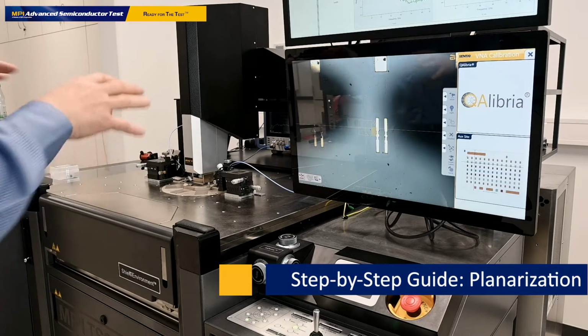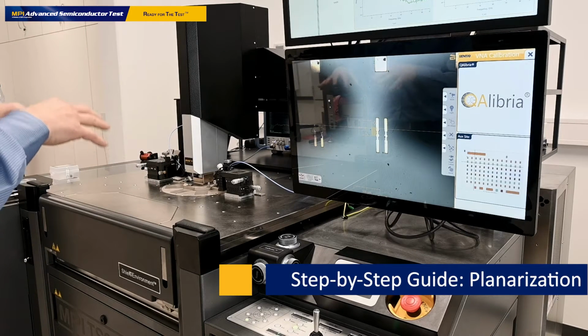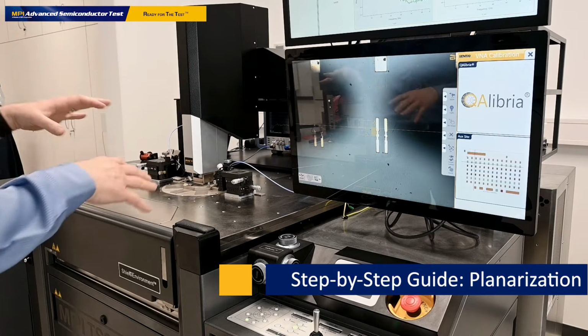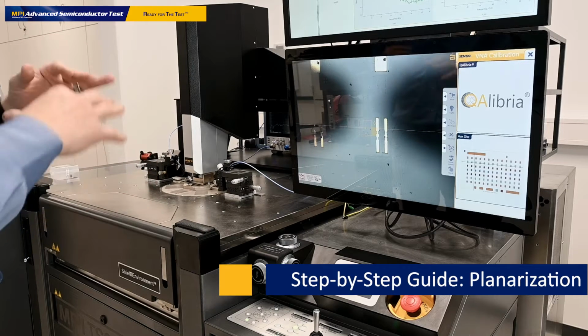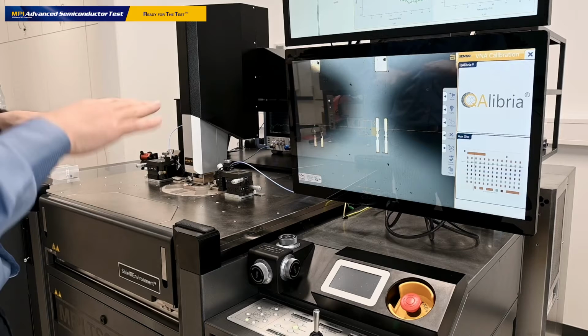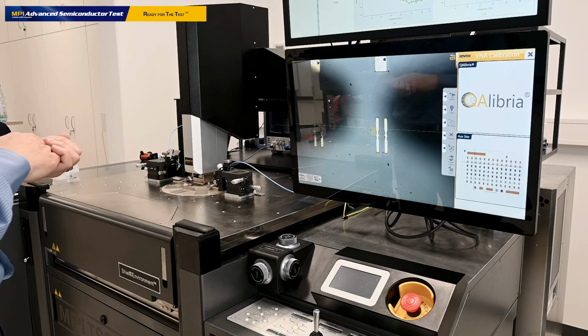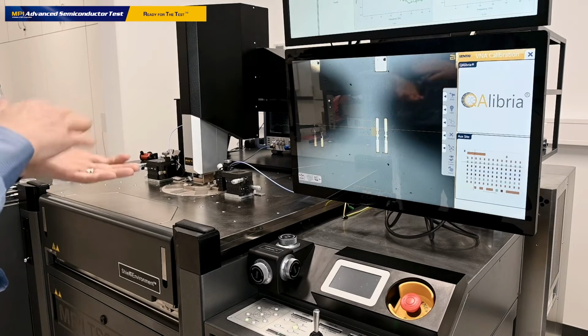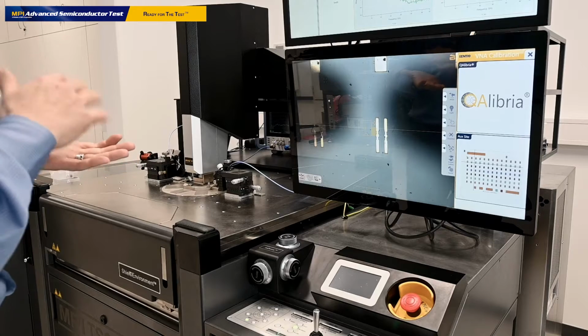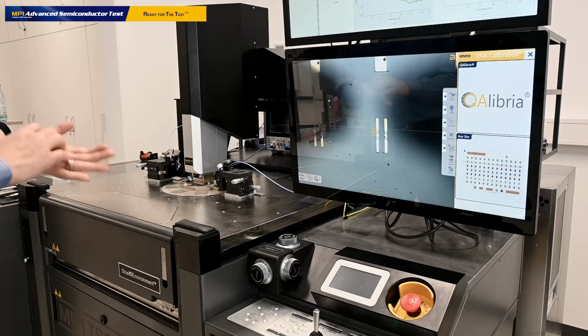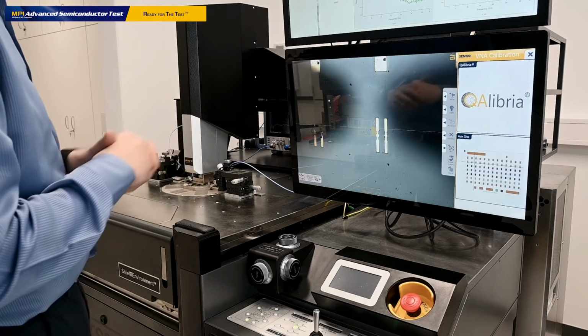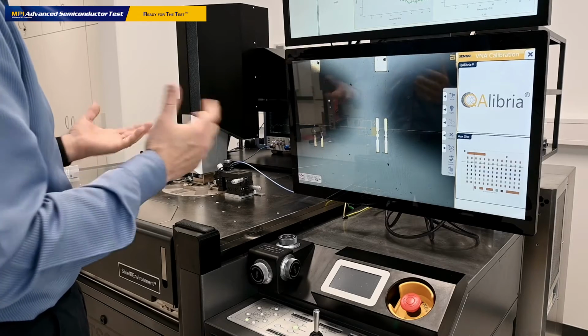So now we've just installed the probes on the positioners, and we close the shield environment. The next step for us is to planarize the probes, because they may be slightly off of the horizontal position, and we need to adjust it, make sure that all contacts, the ground, signal, ground contact, are in place and parallel to this probing area. So how do we do it?